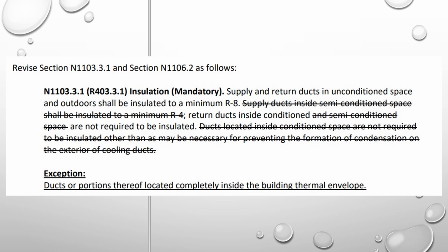All right, so I took a snippet from the North Carolina State Energy Code. Supply and return ducts in unconditioned spaces and outdoors shall be insulated to a minimum of R8 ductwork, which is what we do. This is what we wrap our ductwork with.